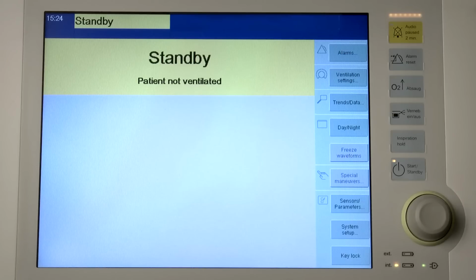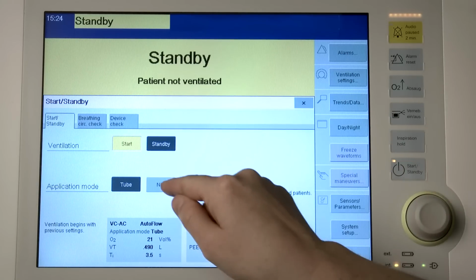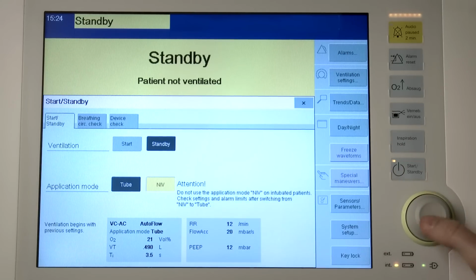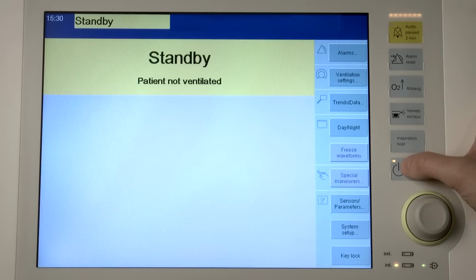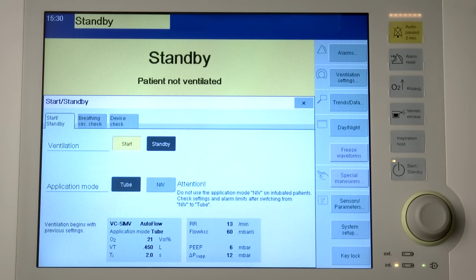Savina 300 can be used for the ventilation of intubated patients in application mode tube and for non-invasive ventilation in application mode NIV. Open the Start Standby page while Savina 300 is in standby mode and touch the tube or NIV button. Confirm with the rotary knob. In the NIV application mode, an NIV symbol is displayed in the header bar in an orange area. To start ventilation, press the Start Standby key.